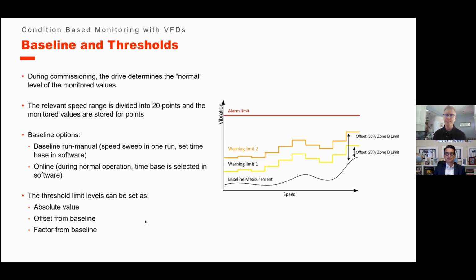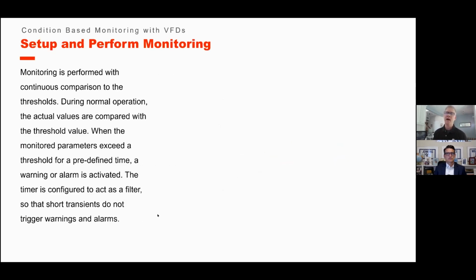If you really know your machine and you know your levels, you can certainly set your absolutes in. A lot of people will do vibration testing as a regular basis on a motor. You get a new bearing, number of bearings, et cetera. You do vibration testing. So you might know your absolutes there, but I doubt you're going to know your absolutes when it comes to motor winding theory or any of that information inside an electric motor. Load, you may know your load envelope absolutes, but you have a choice of absolutes, offset, or factors based off the baseline. How do you set up and perform this?